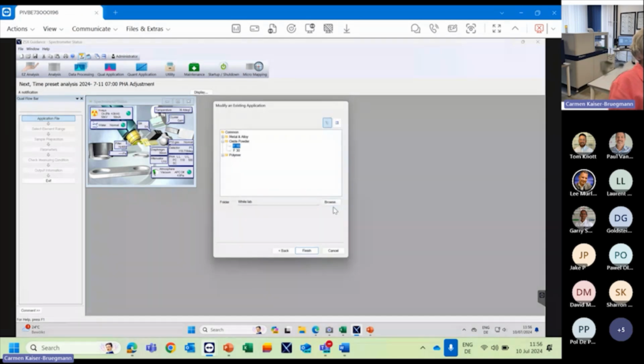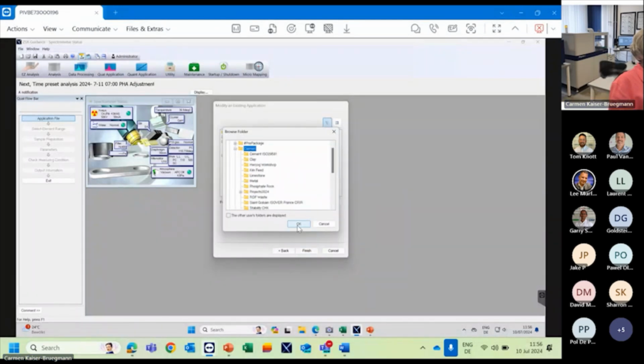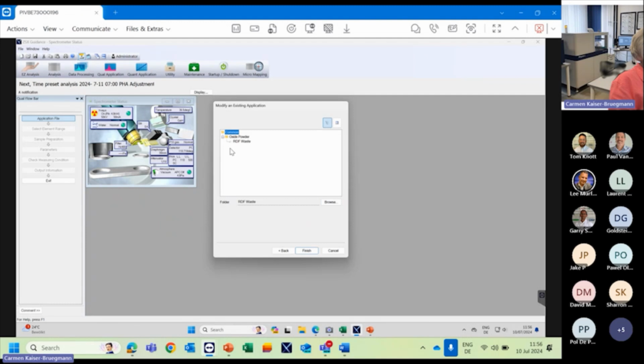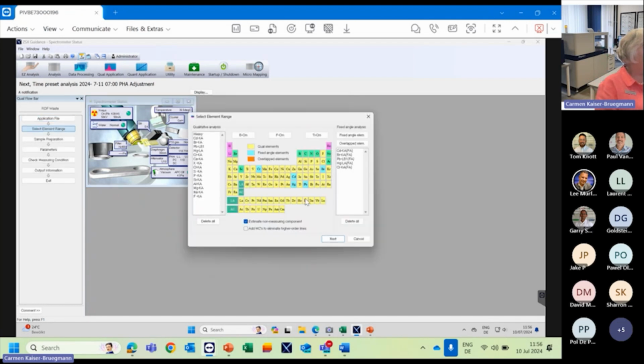So here we have, for example, a waste sample, and the waste sample needs to be analyzed by semi-quant because we don't have a calibration method for it. So I called it refuse-derived material. Here you can see this very nice flow bar that Paul was talking about earlier, where we can select and develop the method step by step. For example, here we have a measurement of all the yellow elements as qualitative, and then we have the blue ones as fixed angles.